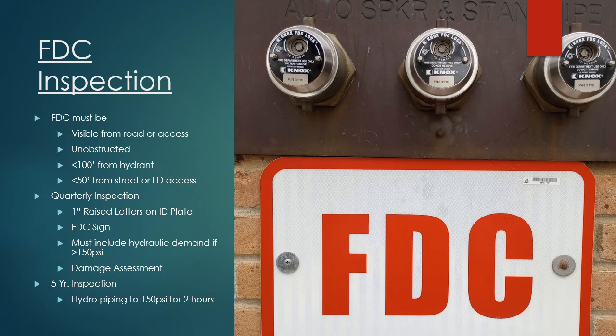Every 5 years, the FDC piping from the connection to the system is to be hydro tested and visually inspected—anything that is easily accessible—to 150 psi for 2 hours.